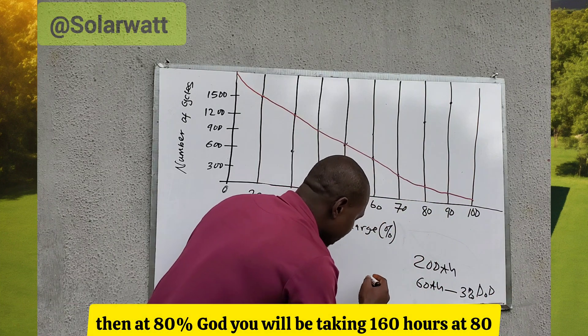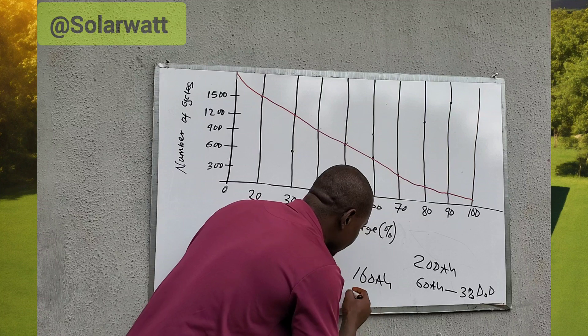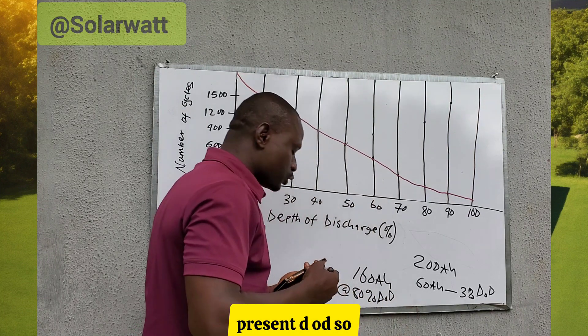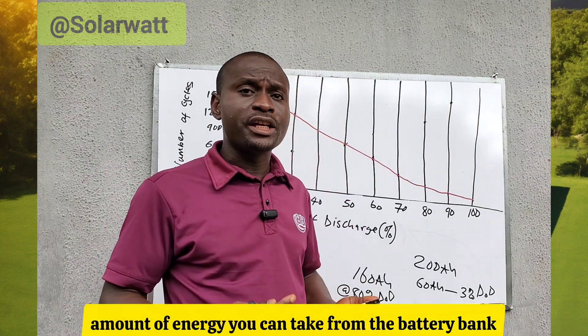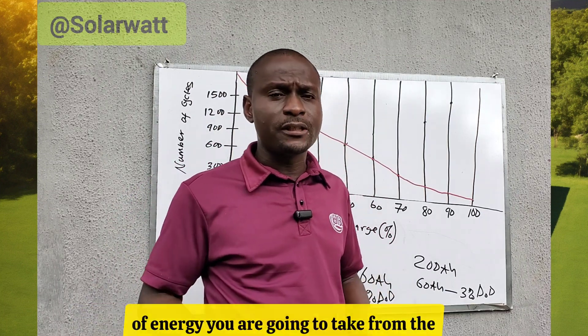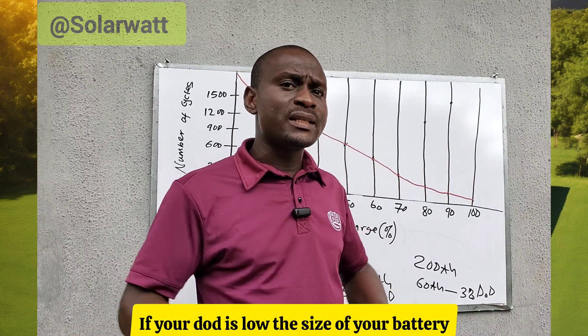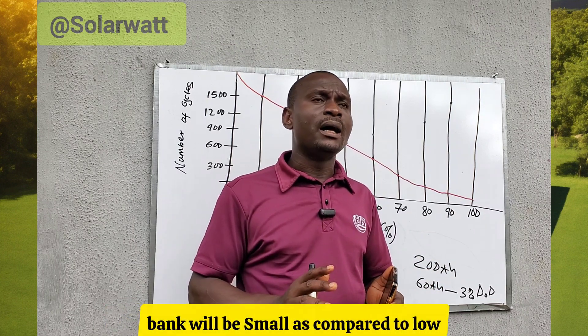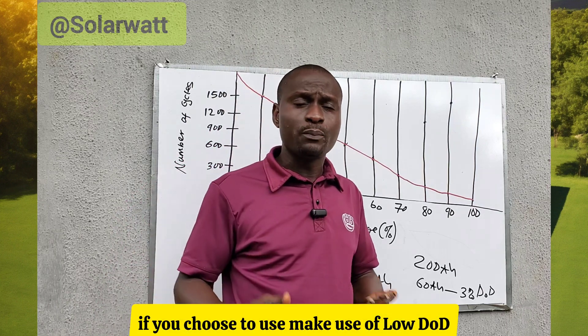At 80% DoD you would be taking 160 amp-hours. The higher the DoD, the higher the amount of energy you can take from the battery bank, and the lower the DoD, the lower the energy available. Also, if your DoD is low, the size of your battery bank will be large; if your DoD is high, the battery bank size will be smaller compared to using a low DoD.